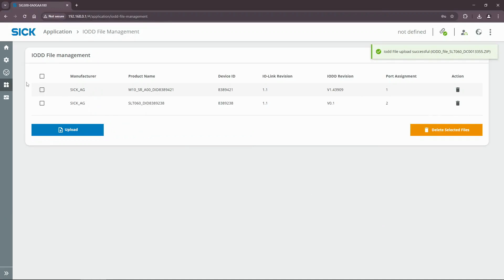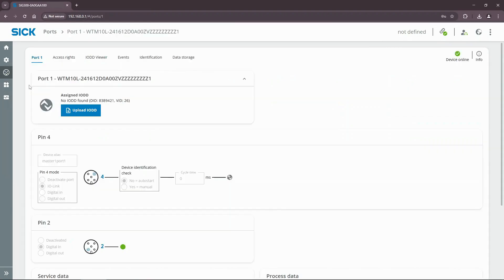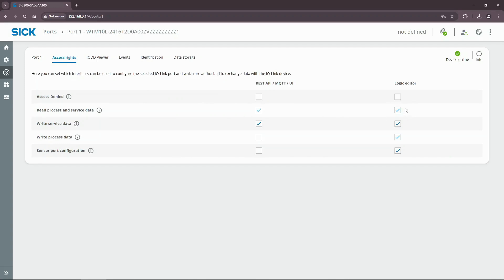Now we need to configure the IO-Link ports. Select port 1 from the ports list menu. Open the access rights tab and make sure that read process and service data is enabled for the logic editor. Also enable the sensor port configuration for the REST API to configure the port settings.